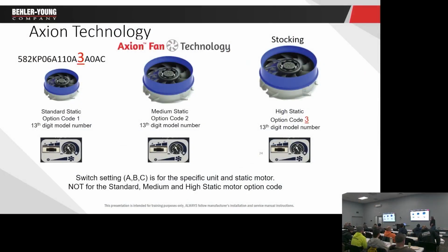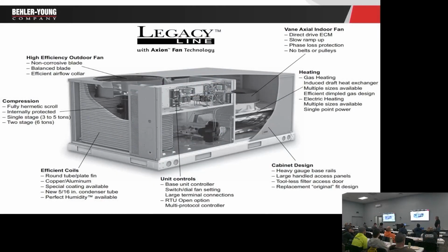Okay, so we're going to look at this motor here. Again, all the rooftop units have standard static, medium static, and high static. Okay, most of the time on the bigger units, we have the medium or we stock the high. On the old belt drive motors, if I had a medium static unit and I needed high static, I could change a blower motor. That doesn't work with these, okay, because it's not just the motor that's different. All right, the entire assembly is different. The wheel's different, the motor's different, so it's not so easy to move a medium static unit and convert it to high static. Okay, so the larger units, so this is the 7.5 ton to 15 ton.